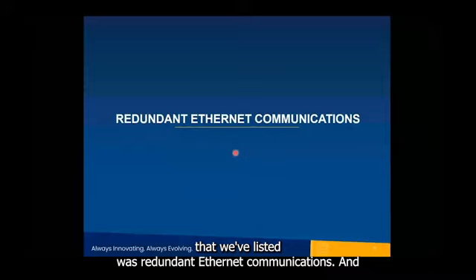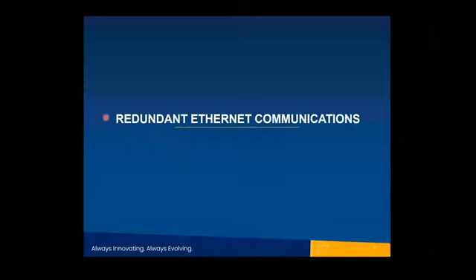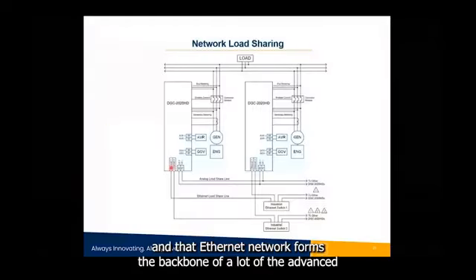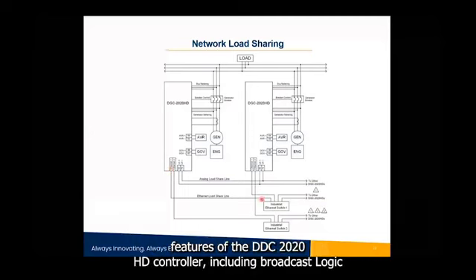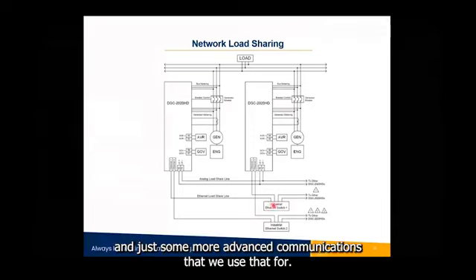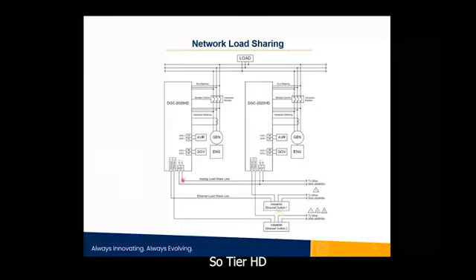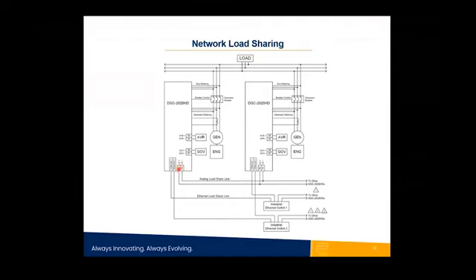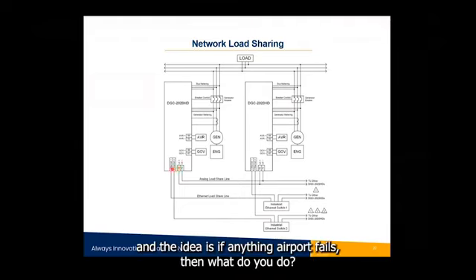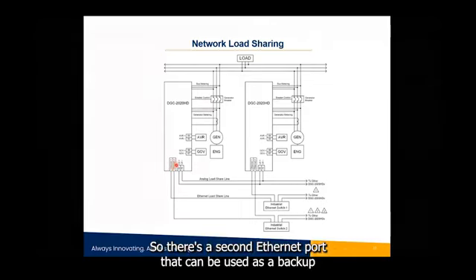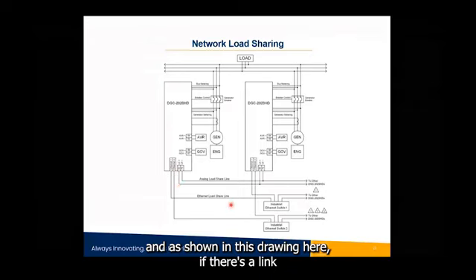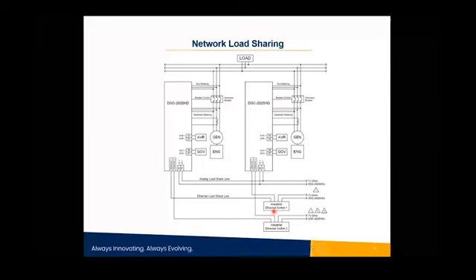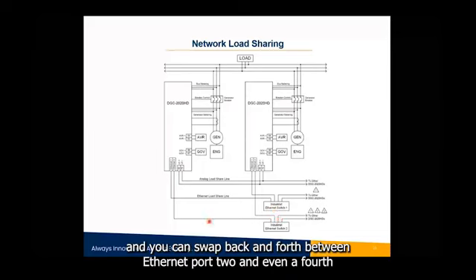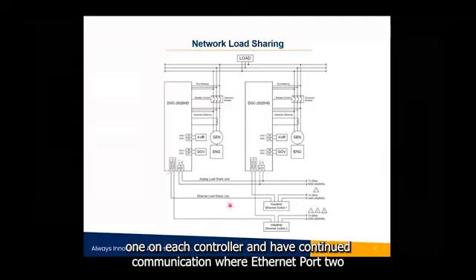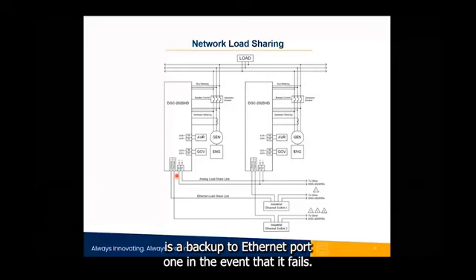Another key requirement that we listed was redundant Ethernet communications. Like I said, we use Ethernet for load sharing, and that Ethernet network forms the backbone of a lot of the advanced features of the DGC 2020 HD controller, including broadcast logic and some more advanced communications. Here, each DGC 2020 HD is shown having 2 Ethernet ports. The idea is, if an Ethernet port fails, then what do you do? There's a second Ethernet port that can be used as a backup.